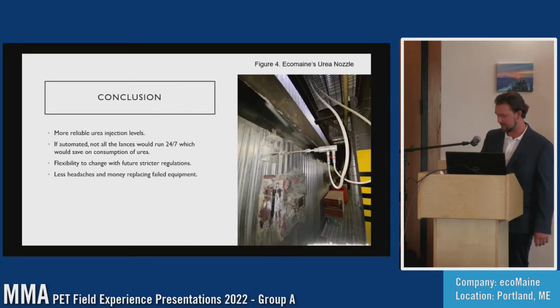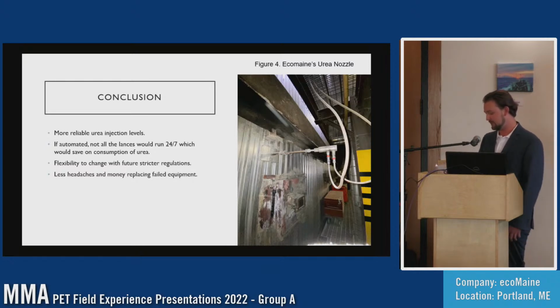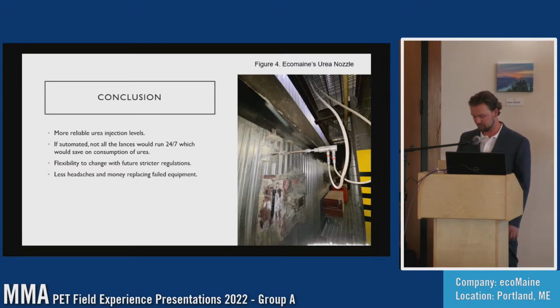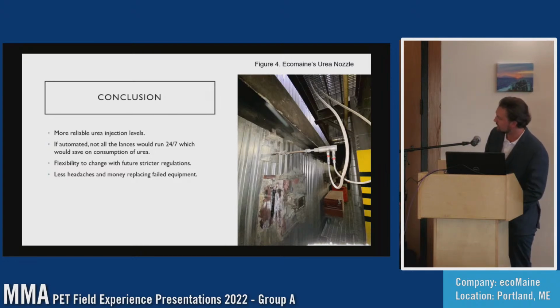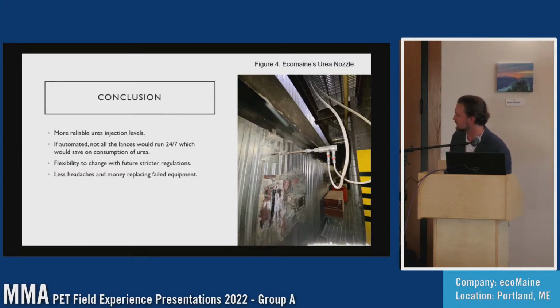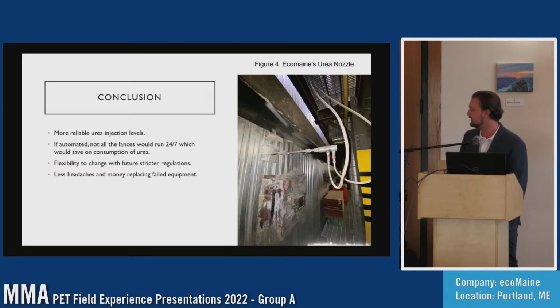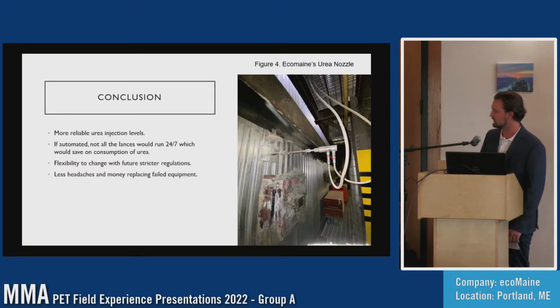In conclusion, the newer SNCR system would be way more reliable with multiple injection points. The lances would be automated, which would mean they would not run all the time, which would make them last longer, and the consumption of urea would also be minimized. Maine will have more flexibility with future stricter regulations, and there will be less time spent troubleshooting and replacing failed equipment. The picture here is what one of our current lances looks like. There's 2 of them on each side. And there would be 3 lances instead of 2 on 2 different levels. That's it.